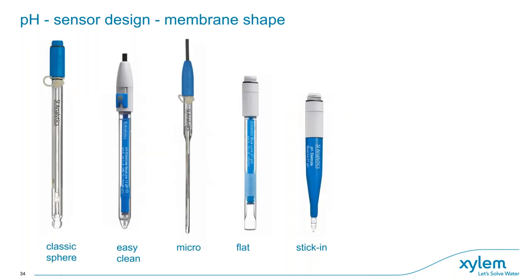Regarding membrane shape: the classical sphere from a glassblower has a large surface area, which is an advantage. Flatter, more modern shapes are easier to clean and still provide normal measurements. Micro electrodes are used for low-volume samples, for example measuring small amounts of blood. Flat membrane electrodes can measure on surfaces such as skin.